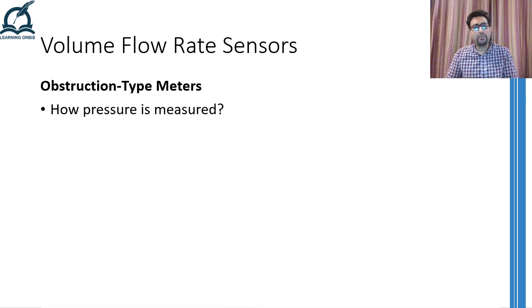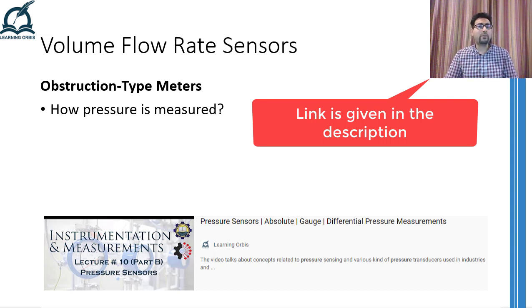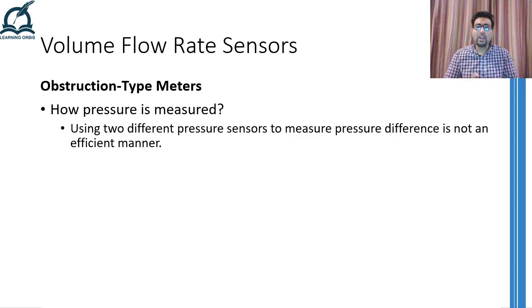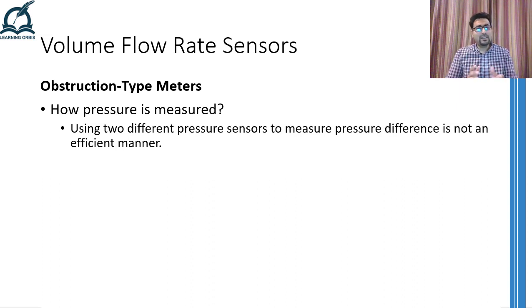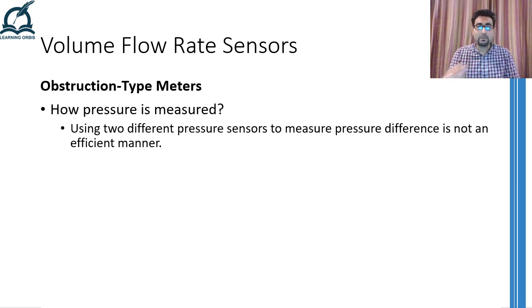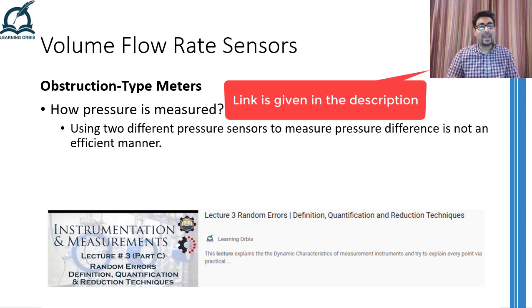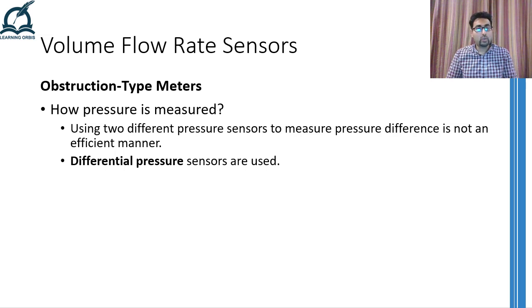The second question is how to measure pressure before and after the obstruction so that the pressure difference can be figured out. I have discussed a range of pressure sensors in the reference video, so you can consult that for details. However, using two separate pressure sensors to measure pressure before and after the obstruction and then calculating the pressure difference is not an efficient way, because measurement errors in both individual sensors will be added up. Therefore, it is highly recommended to use a differential pressure sensor, which is capable of giving you the pressure difference directly.